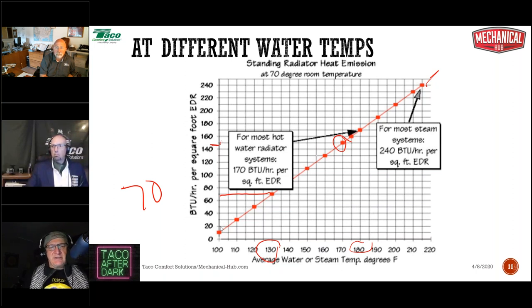But what you're seeing there, and this is a good question, Peter, the difference between 4 gallons a minute and 1 gallon a minute at 180 degree water is about 30 BTUs per foot. If it was much less than that, you probably, first off, try to run less than 1 gallon a minute through anything. It's kind of hard. So I'm sure the output would be a little bit lower, but not that much. All righty, very good.